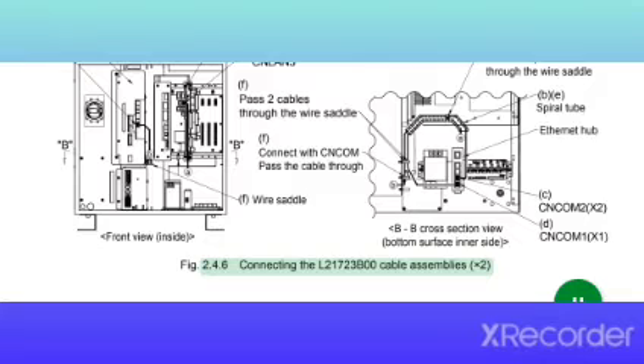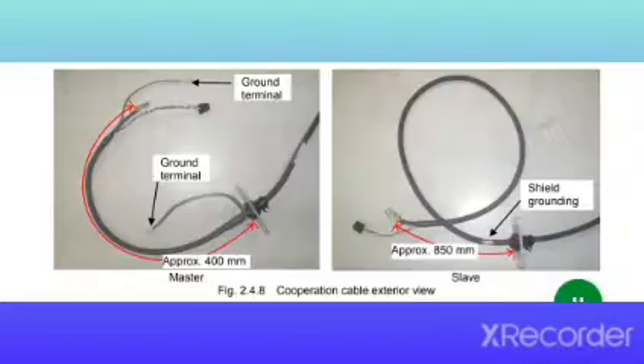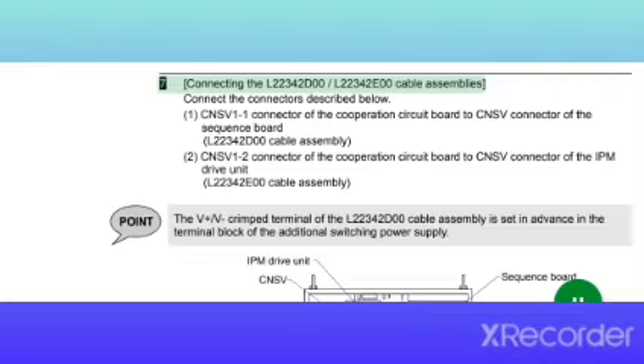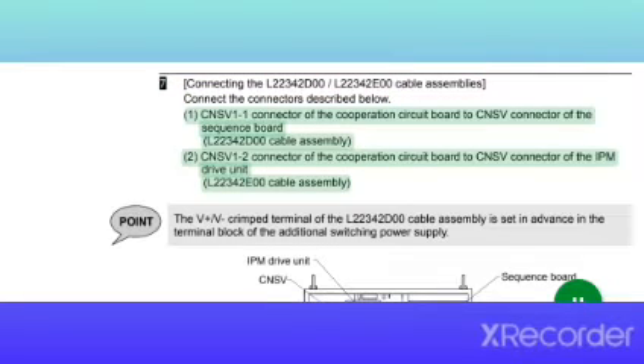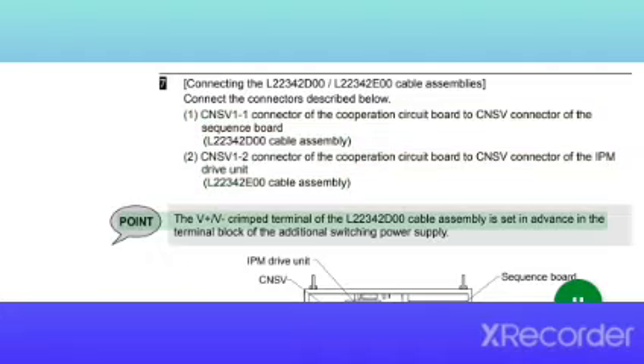2.4 Cooperation kit connection and power on methods, 2 to 14. 7. Connecting the L22342D00/L22342E00 cable assemblies. Connect the connectors described below. 1. CNSV1-1 connector of the cooperation circuit board to CNSV connector of the sequence board, L22342D00 cable assembly. 2. CNSV1-2 connector of the cooperation circuit board to CNSV connector of the IPM drive unit, L22342E00 cable assembly.